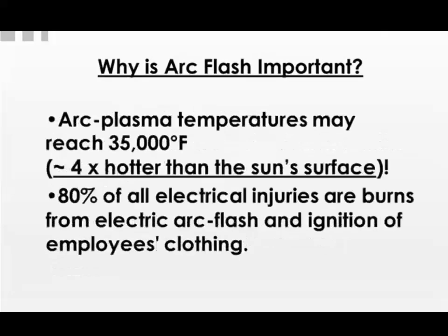Why is arc flash important? Well, arc plasma temperatures, when the arc flash or arc blast occur, can reach temperatures that are 35,000 degrees. Let me repeat that, 35,000 degrees. I've done this awareness training a number of times now, and that is still hard for me to wrap my brain around, how hot that is. That is literally almost 4 times hotter than the sun's surface. Any material known to man or woman vaporizes at that temperature.